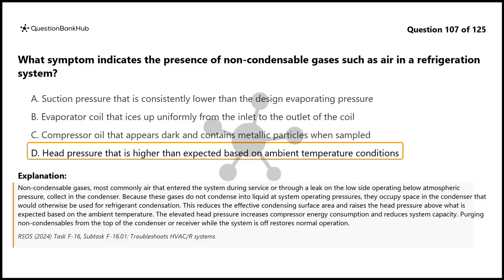This reduces the effective condensing surface area and raises the head pressure above what is expected based on the ambient temperature. The elevated head pressure increases compressor energy consumption and reduces system capacity. Purging non-condensables from the top of the condenser or receiver while the system is off restores normal operation.